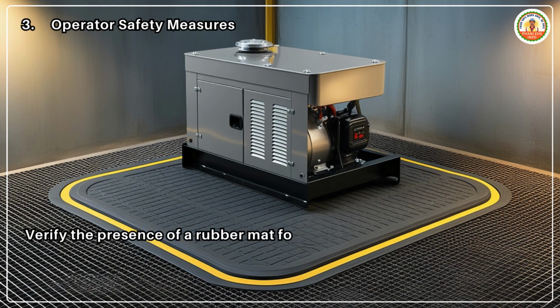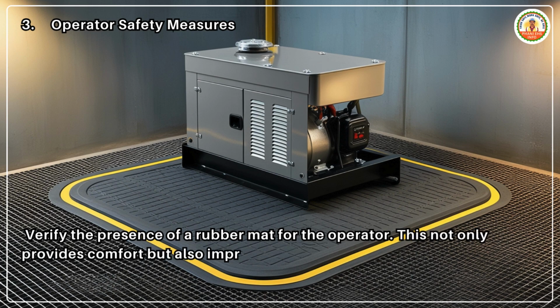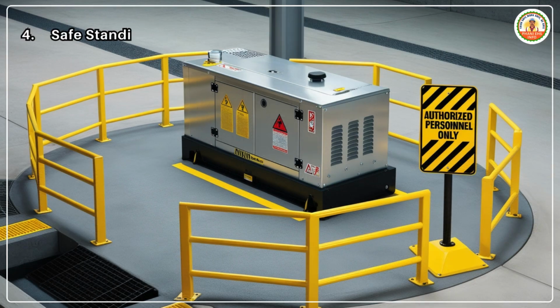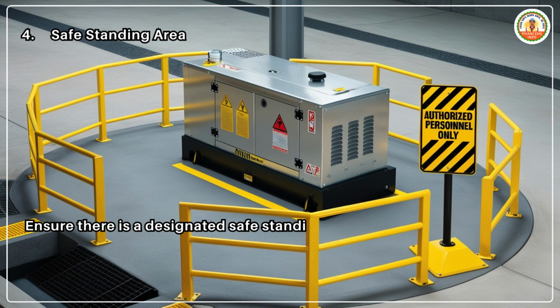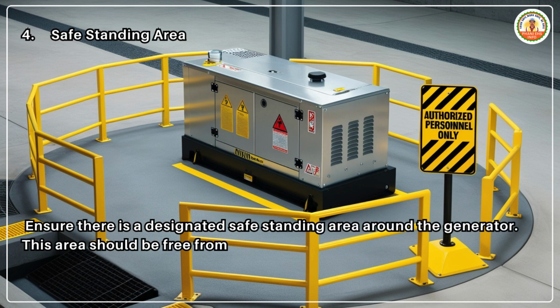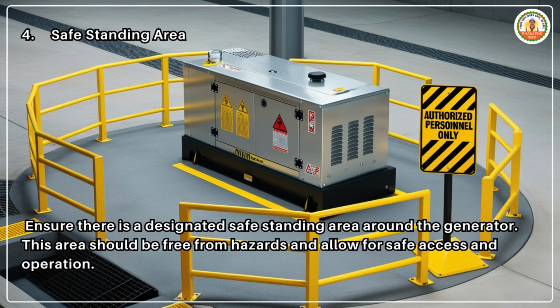3. Operator safety measures. Verify the presence of a rubber mat for the operator. This not only provides comfort but also improves safety by reducing the risk of slips and falls. 4. Safe standing area. Ensure there is a designated safe standing area around the generator. This area should be free from hazards and allow for safe access and operation.